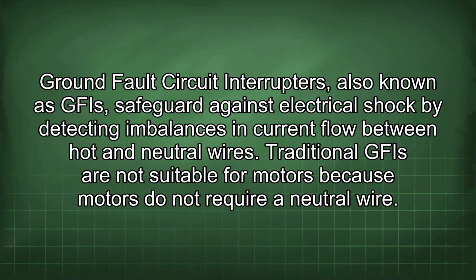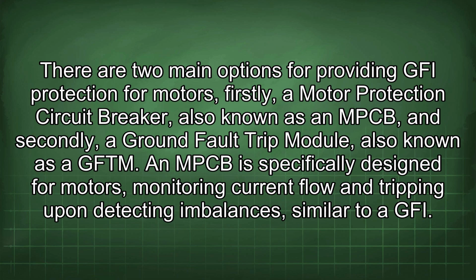Ground fault circuit interrupters, also known as GFI, safeguard against electrical shock by detecting imbalances in current flow between hot and neutral wires. Traditional GFI are not suitable for motors because motors do not require a neutral wire. There are two main options for providing GFI protection for motors.